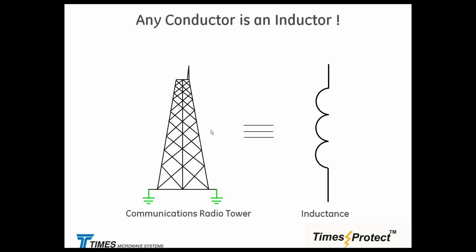Remember the rate of rise time of that current, the di/dt. If you want to figure out what inductive voltage drop we are going to experience, you simply take the inductance of the tower or the cable and factor that into the rate of rise time and peak value of the current to figure out the total amount of inductive voltage drop across it. So basically every conductor in the air will become an inductor, especially with a di/dt.